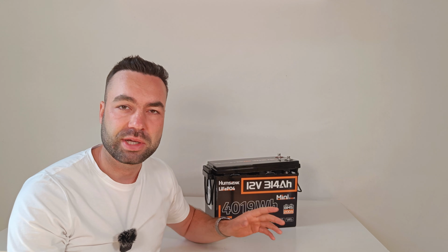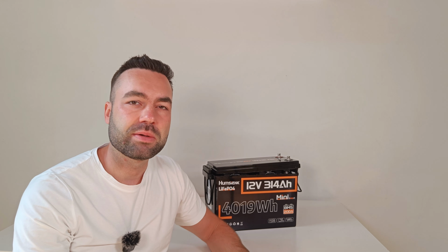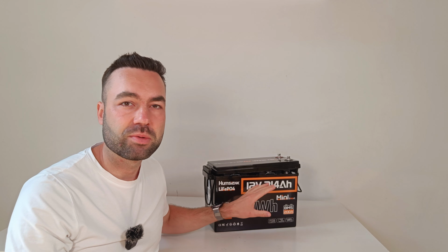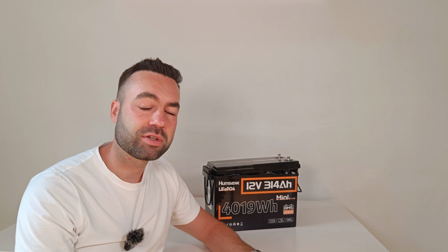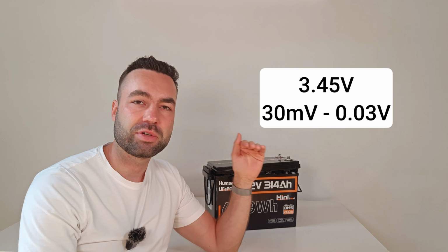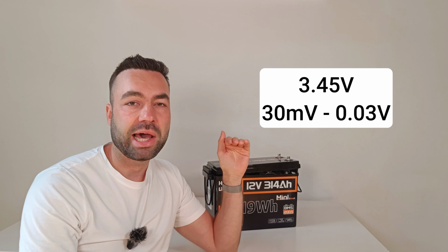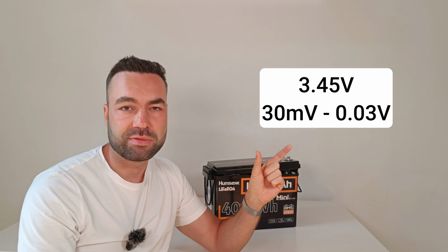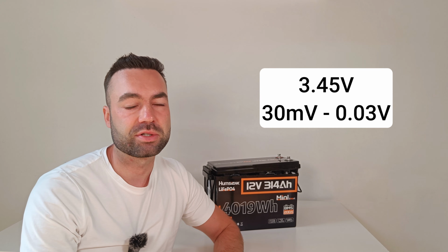So what can you do if you have this battery? First, check whether your battery actually has the problem, since not every unit may be affected. Test whether it balances without an active charge. Remember that cell voltages need to be above 3.45 volts, and the difference between the cells must be at least 30 millivolts before balancing starts.